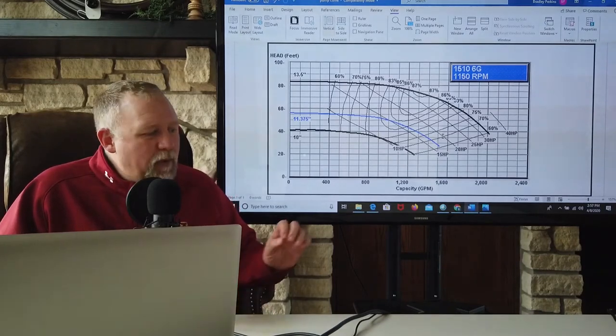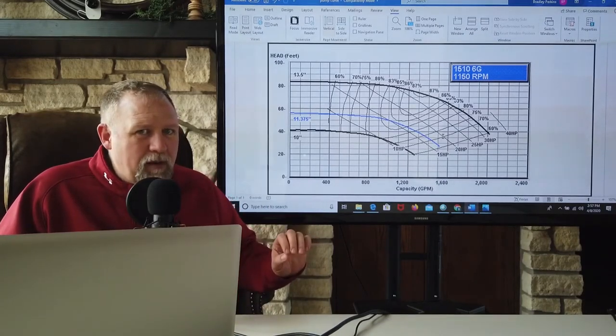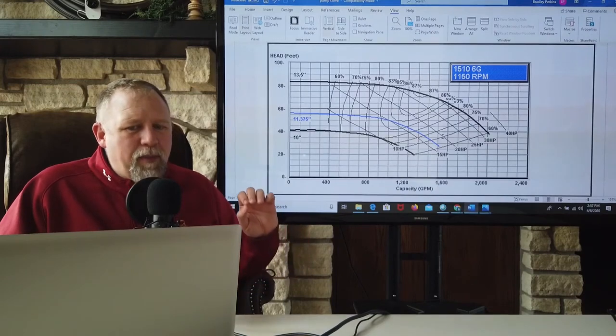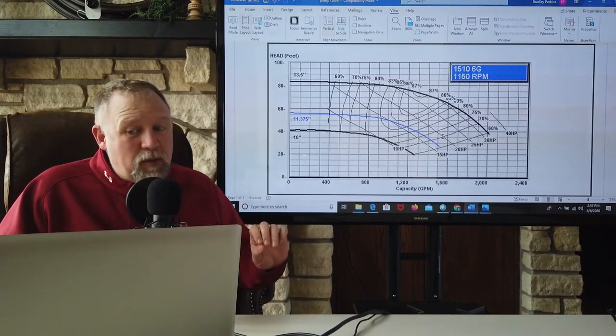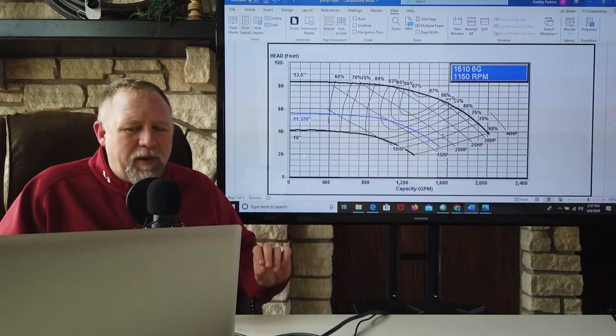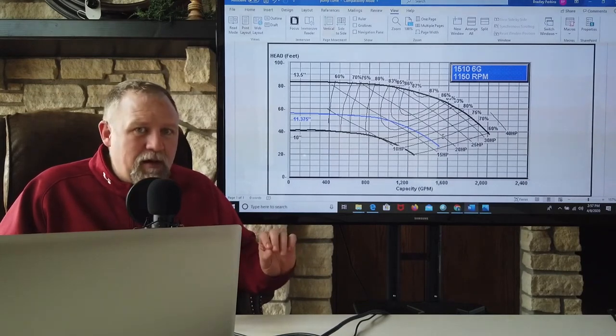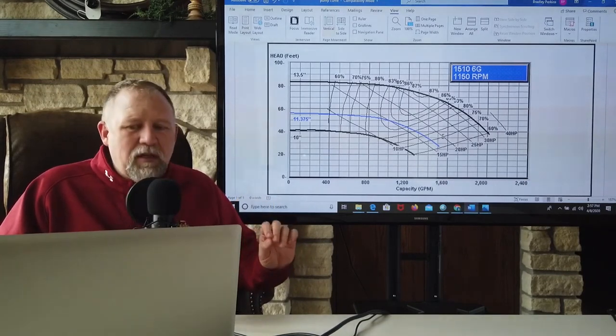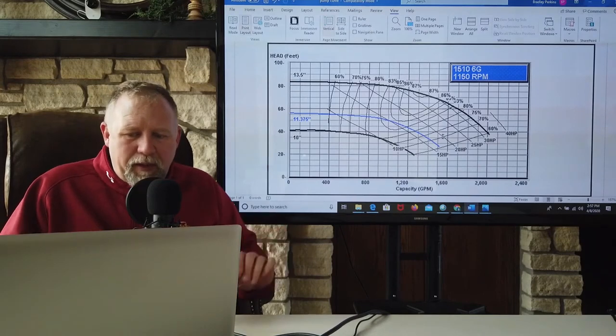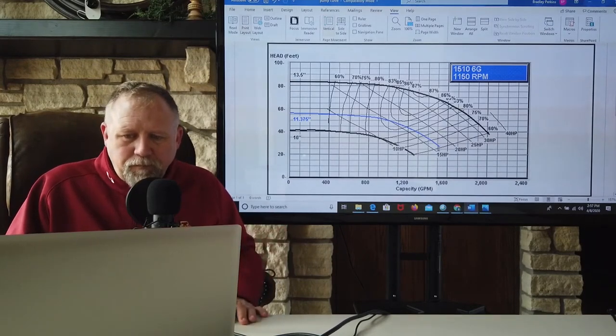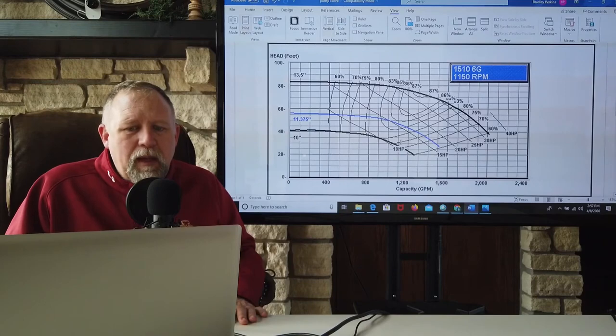In other words, if a motor is rated for 20 horsepower, why would we want to operate it above 20 horsepower or even right at 20 horsepower? It will last a lot longer if we don't push it close to its rated duty point. All right.